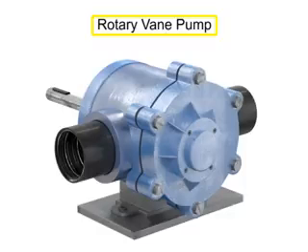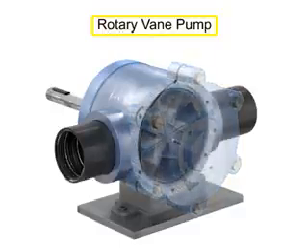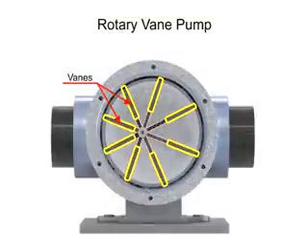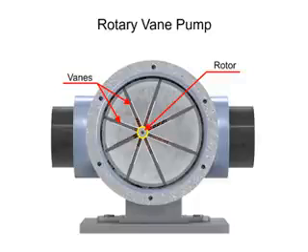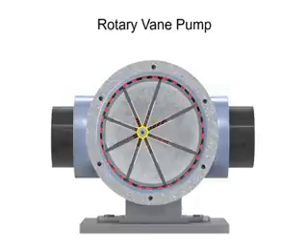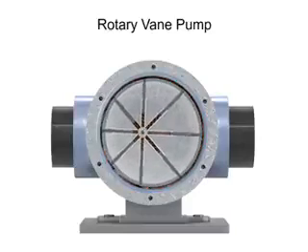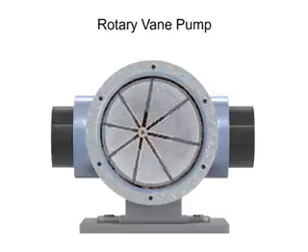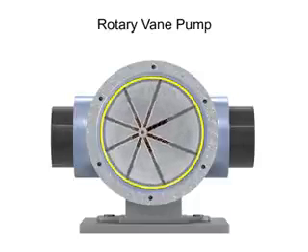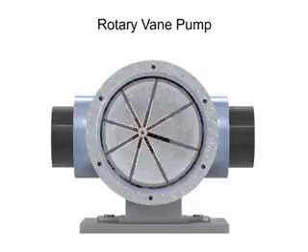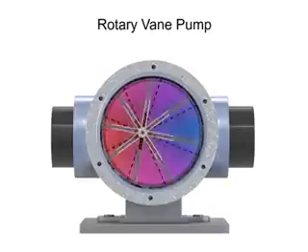A rotary vane pump is a positive displacement pump that consists of vanes mounted to a rotor. The vanes are on an off-center drive shaft. As the shaft rotates, the variable length vanes slide in and out to maintain contact with the pump housing. The tension in the vanes is maintained by either springs or hydraulic pressure, and as the vanes rotate, they create chambers of varying sizes within the pump.